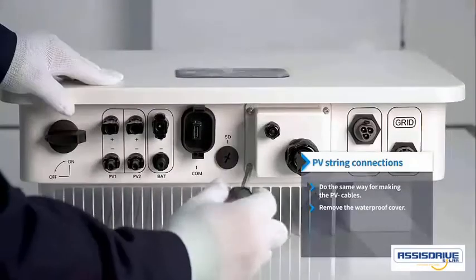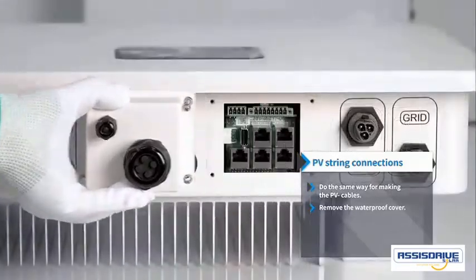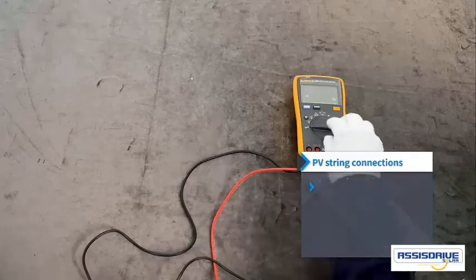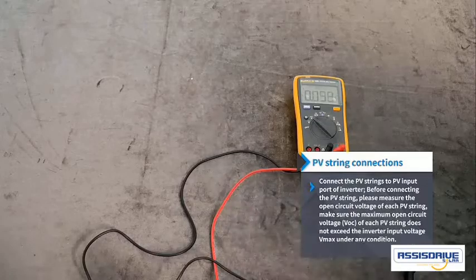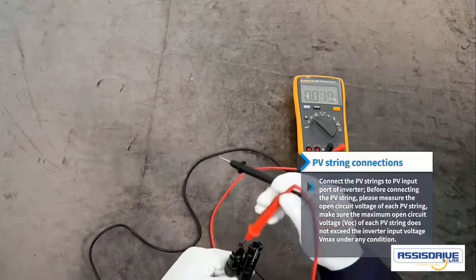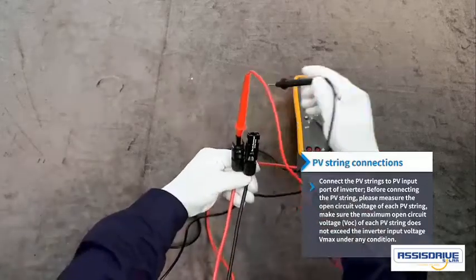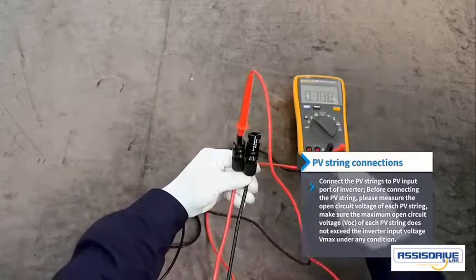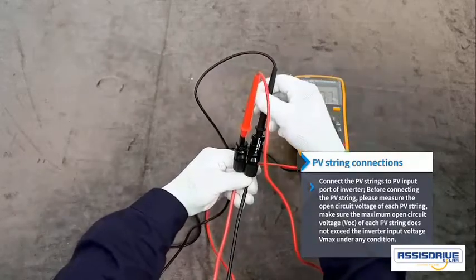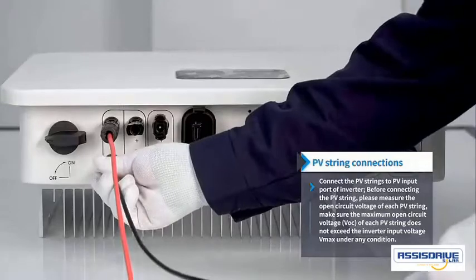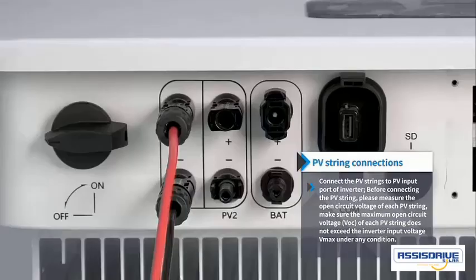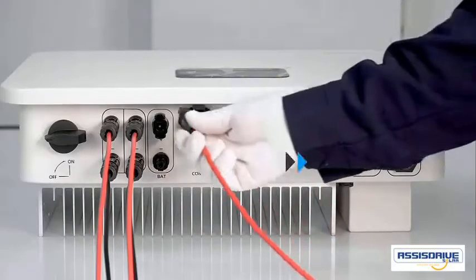Remove the waterproof cover. Connect the PV strings to PV input port of inverter. Before connecting the PV string, please measure the open circuit voltage of each PV string. Make sure the maximum open circuit voltage, VOC, of each PV string does not exceed the inverter input voltage max under any condition. Battery connections.